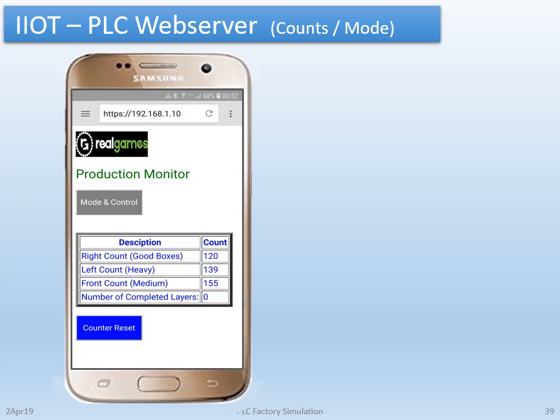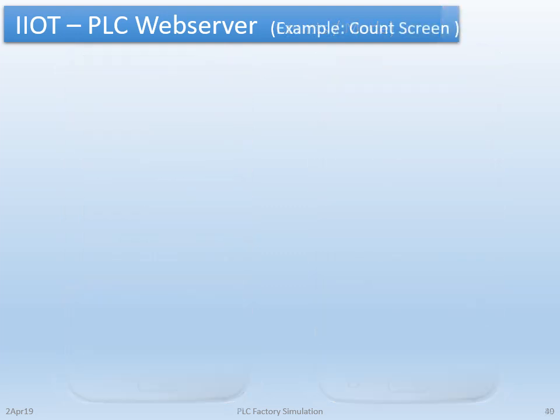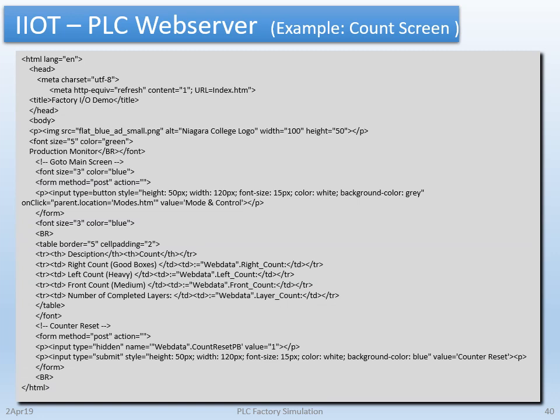The cool thing about the S7-1200 PLC is that it has a built-in web server. So with some very simple HTML code, I can create a basic screen with some usefulness. The left screen here shows a display of the box count, number of completed layers, as well as allowing a counter reset function. The right screen is the mode and system start control screen — automatic, manual reset, run, stop, and system reset are all available, as well as a simple status of each of the major functions and a basic alarm or system message. Using a very basic table format to display data for the count screen allowed this to be the entire HTML code, including the counter display, reset button, and buttons to switch to the next screen.